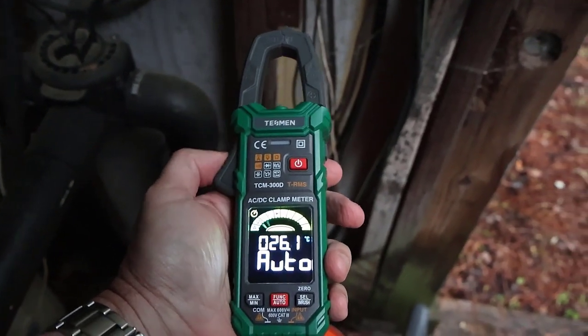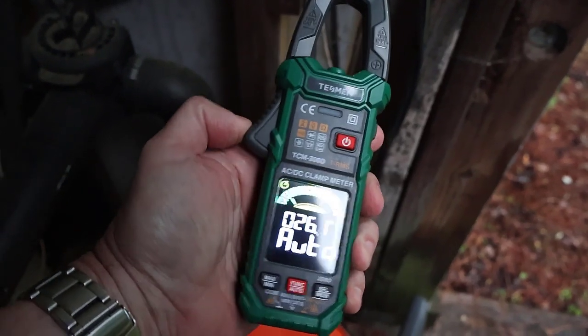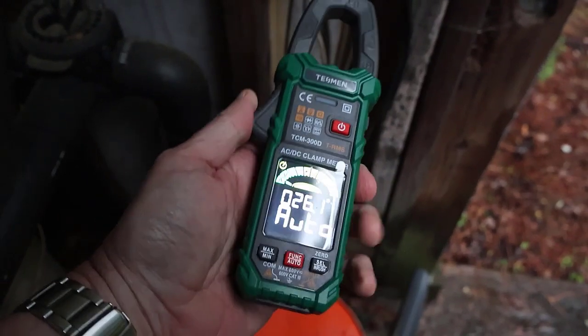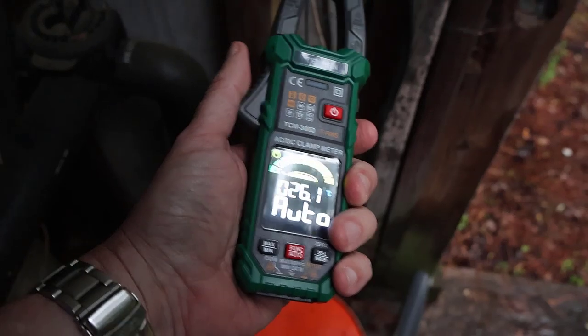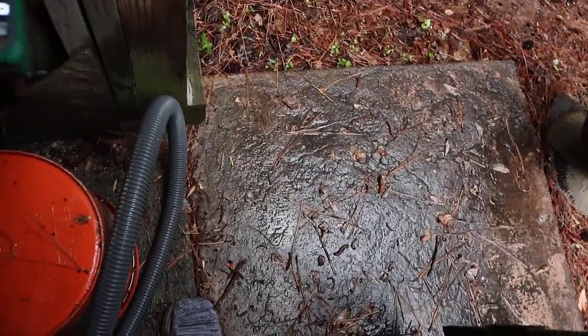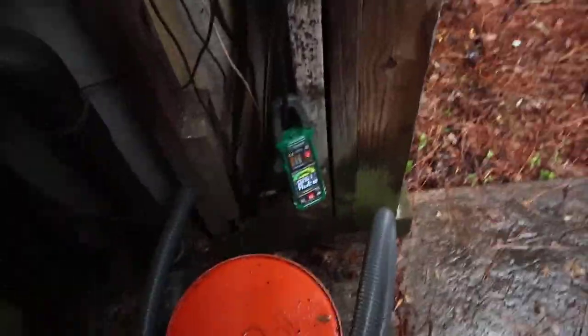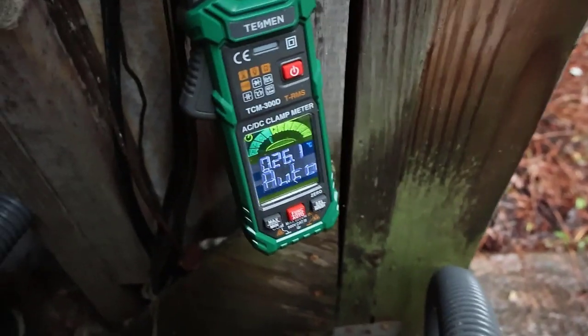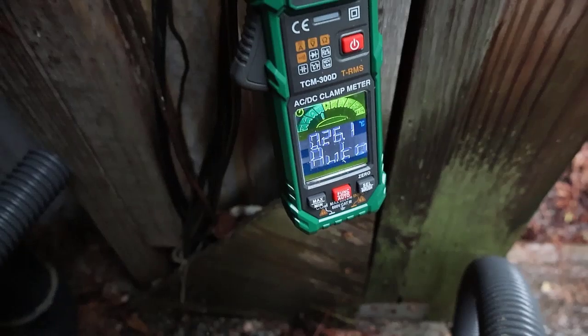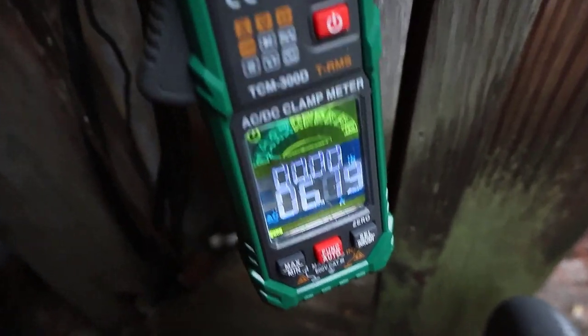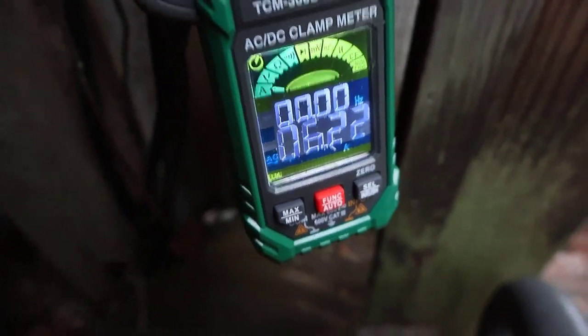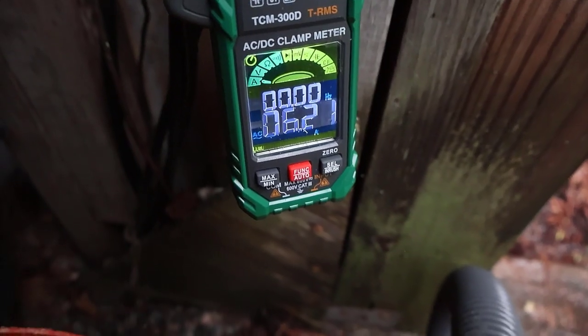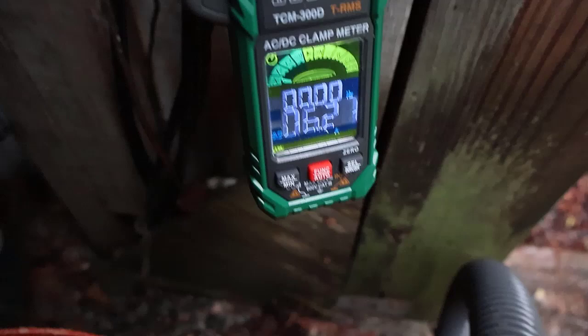Now how to use the amp meter. The clamp side measures the current of an insulated wire. But you can't just put it around an extension cord, because the incoming wire and the neutral will cancel each other out. My leads are right here, and I'll make sure one of them is clamped, since a 220 system splits. It's auto ranging, which is really nice because you don't have to think about anything, and that's one of the things about this. So it's on one of the two leads, measuring the amps in that. When I turn on my pool pump to draw some amperage, you'll see it's drawing over 6 amps on that leg. If I clamp it on the other leg, it'll draw the same exact amount, because my pool system is a 220, 240 system. Pretty cool that it can do that.